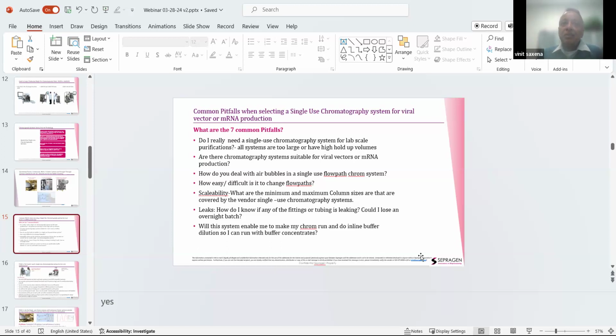Are there chromatography systems suitable for viral vectors or mRNA production? Then things like, how do you deal with air bubbles in a chromatography system? In larger systems you may have bubble traps, well, large holdup volume, so we'll discuss that. And how easy or difficult is it to change flow paths? And then scalability: what are the minimum and maximum column sizes covered by the vendor's single-use chromatography systems? Then, if you're using single-use chromatography systems, how do I know if there are leaks? What do I do with that? If I'm running an overnight run, can I lose my batch?